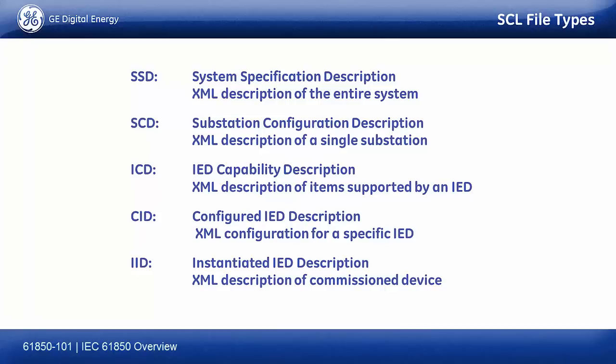Okay, we go through the SSD file, which is a system specification description file, which describes the whole system. The SCD file is the master file for a substation, the substation configuration description. It's the XML description of a single substation and everything in it, right?